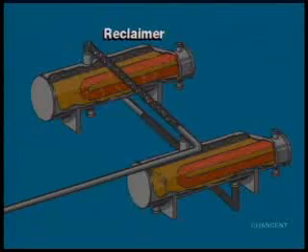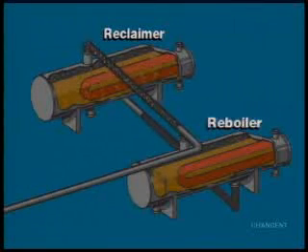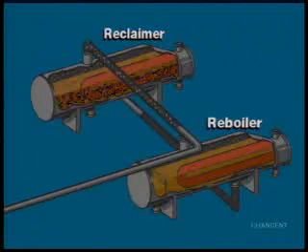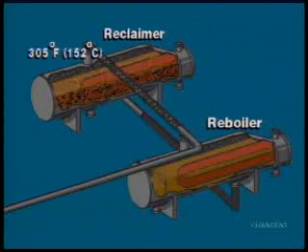A side stream of 1 to 3% of the total amine circulation is fed from the reboiler to the reclaimer. Amine, which boils from the top of the reclaimer, flows to the vapor outlet of the reboiler. As amine in the reclaimer continues to boil out, the concentration of contaminants will increase, and liquid temperature in the reclaimer will also increase.